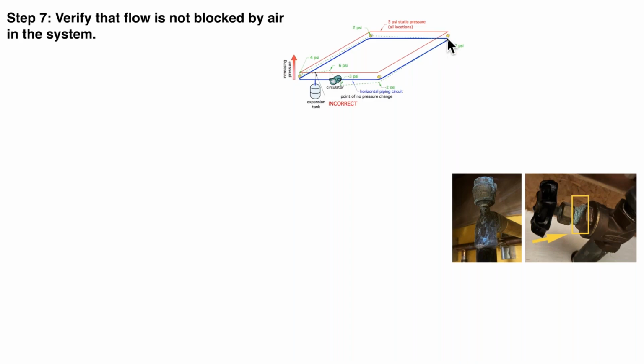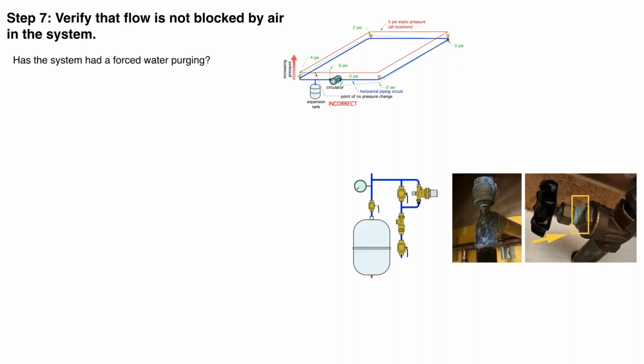If there's any kind of a float type valve there, air vent, anything that could potentially leak air, that system is trying to suck air in. So, that's one of the things to check. Has the system had a good forced water purging? Okay, here's a typical makeup system. I like to put a ball valve in so we can get the highest possible incoming flow rate to really push that bulk air out of the system when we commission it. Maybe somebody hasn't done that.